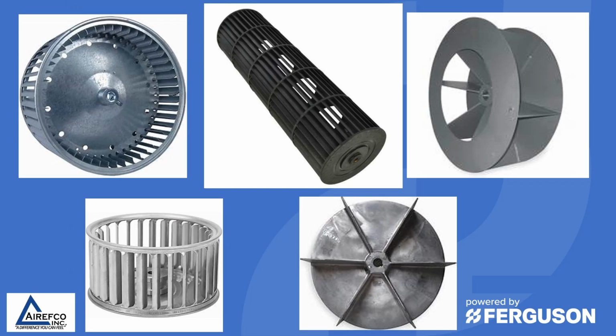Blower wheels come in a variety of shapes and sizes and different configurations. On most of your modern gas furnaces, you either have a single inlet or a dual inlet blower wheel. You need to make sure that these wheels are properly balanced and that they're not vibrating, causing vibration in the furnace or causing noise. And you also need to make sure that they're clean.